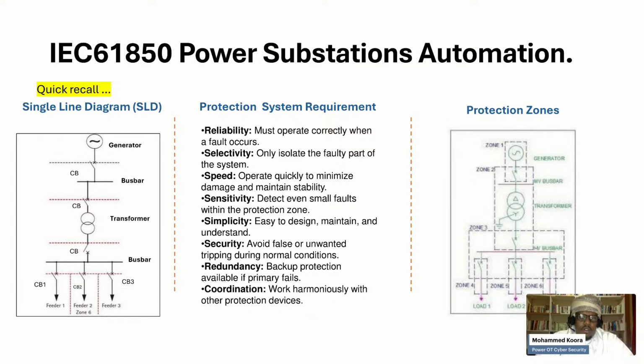Let's talk about coordination on the protection zone side. The zones for protection protect each equipment independently with a different zone, but if you notice, there is some overlap between them. Why do we need that?